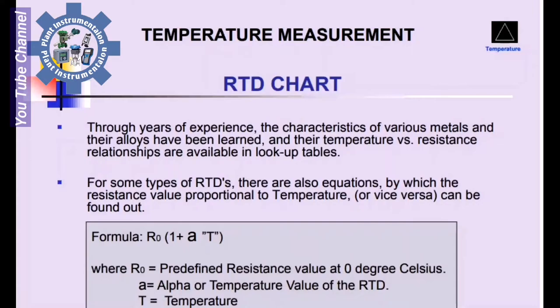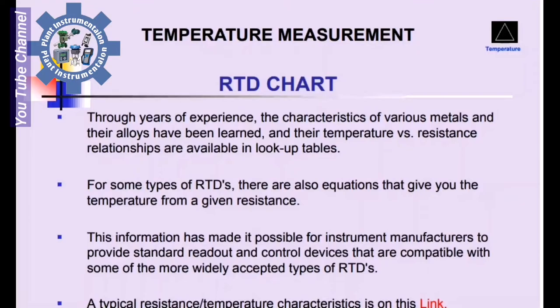For some RTDs, there are also equations by which the resistance value proportional to temperature or vice versa can be found. The formula is R = R0(1 + alpha × T), where R0 is the predefined resistance at 0°C, alpha is the temperature coefficient of the RTD, and T is temperature. This has made it possible for instrument manufacturers to provide standard readout and control devices compatible with widely accepted types of RTDs.